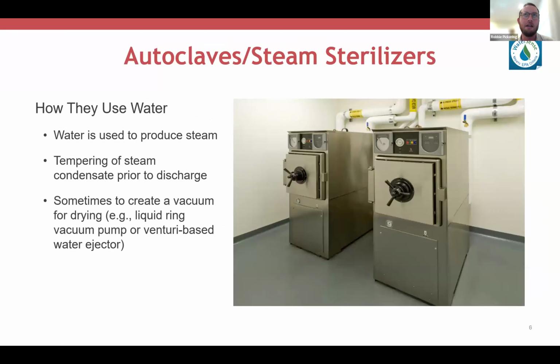Moving on to autoclaves and steam sterilizers. Most lab managers are aware that steam sterilizers are well-known water and energy hogs. They use water in 3 primary ways. First, water is used to produce the steam for the sterilization process. This can usually be either an in-unit boiler or from a centralized boiler system within the lab. Water is also then used to temper the water from the steam condensate that is discharged from the sterilizer.